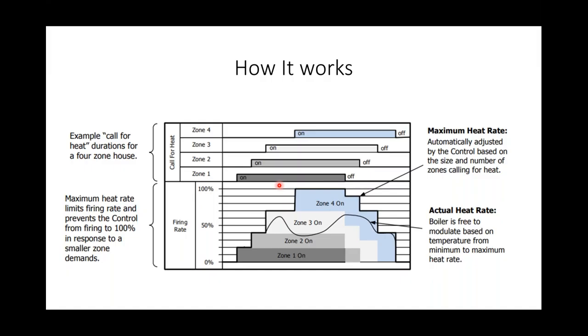So basically, how this is going to work is it's going to find its curve as far as the BTUs of where everything needs to be. Instead of just bouncing all the way up to 100%, it'll float around and it may find that it lives happily at half firing rate. Lower firing rates result in lower fuel use. You tie the Sage panel in with the outdoor reset and the high efficiency modulating condensing boiler, and we've got some real energy savings there. We can really fine tune this system and really get the most efficiency out of the system.